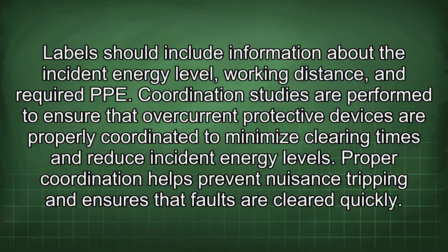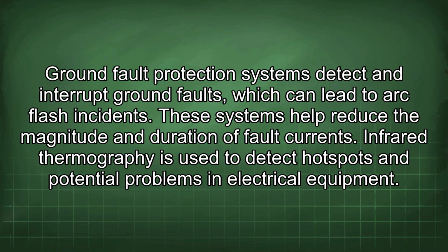Coordination studies are performed to ensure that overcurrent protective devices are properly coordinated to minimize clearing times and reduce incident energy levels. Proper coordination helps prevent nuisance tripping and ensures that faults are cleared quickly. Ground fault protection systems detect and interrupt ground faults, which can lead to arc flash incidents. These systems help reduce the magnitude and duration of fault currents.